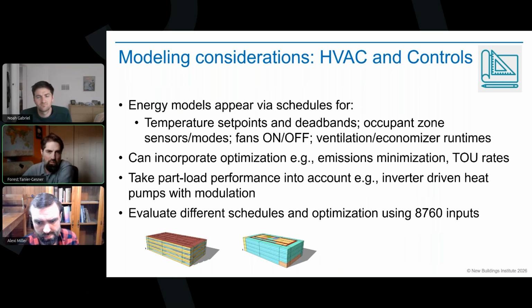Understanding how everything is sequenced matters too. A lot of the potential demand shift depends on how equipment operates at different part load curves and how it's staged to come on - having soft starts on major equipment for a slow ramp, and staging so equipment operates at an efficient point on the part load curve, keeping overall demand as low as possible. That requires close integration with the mechanical design and sequence of operations.